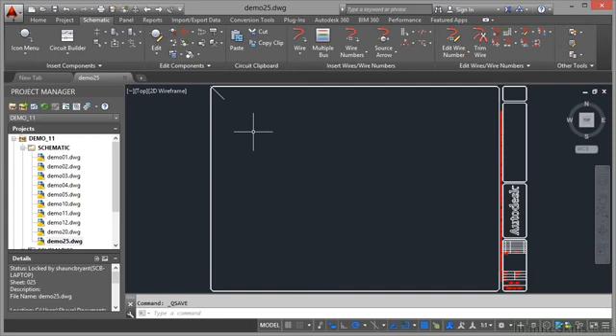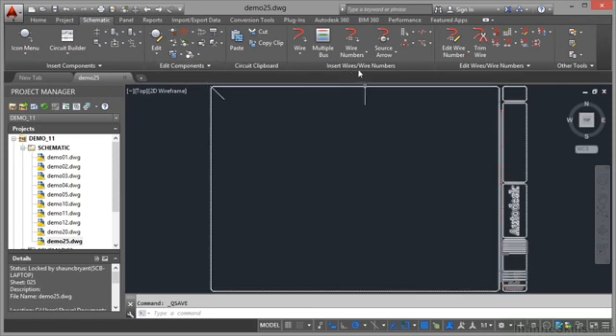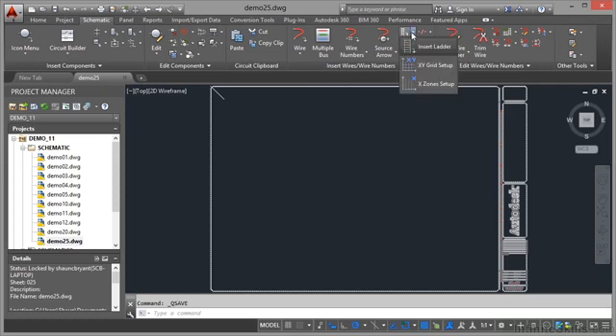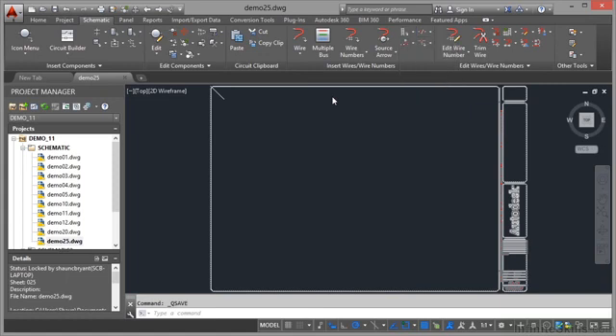Now what you can do is set up grids on your AutoCAD Electrical drawings by way of controlling the drawing properties. So you would have noticed when we went to insert a ladder on the schematic tab in the insert wires, wire numbers panel here, we have the option of an XY grid setup or an X zones setup. The reason you have those different setting up methods is so you can actually tally up the components and the ladders on your drawings. So let's have a look at setting up an XY grid setup first.